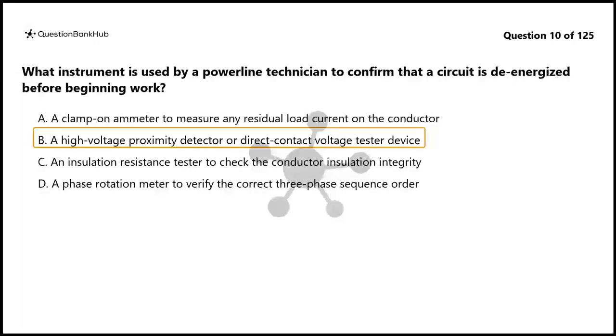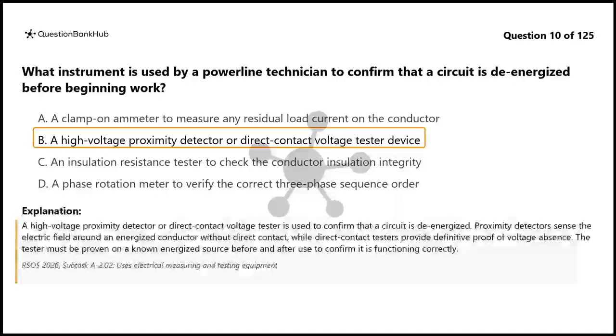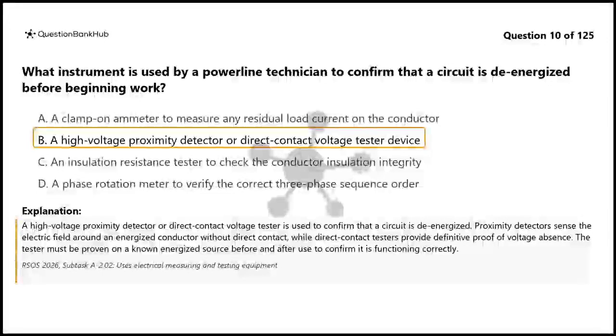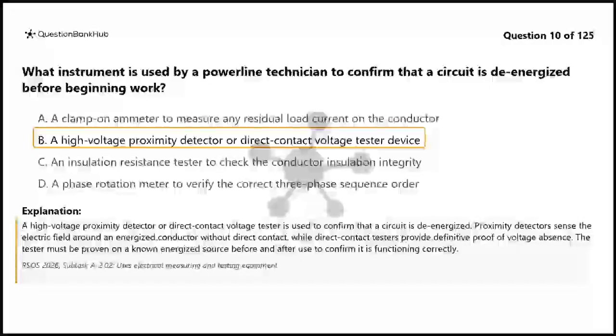The correct answer is B. A high-voltage proximity detector or direct contact voltage tester is used to confirm that a circuit is de-energized. Proximity detectors sense the electric field around an energized conductor without direct contact, while direct contact testers provide definitive proof of voltage absence. The tester must be proven on a known energized source before and after use to confirm it is functioning correctly.